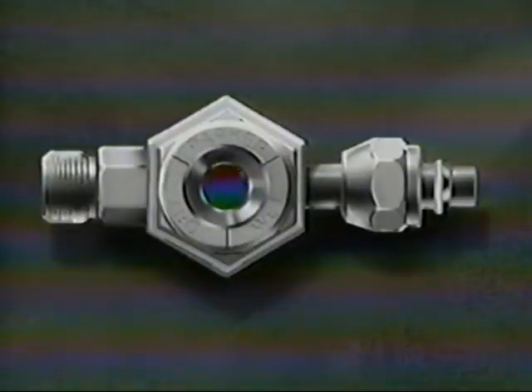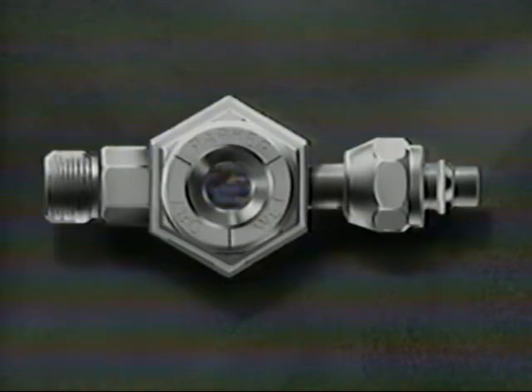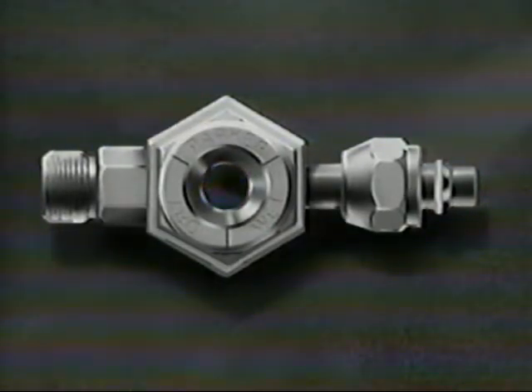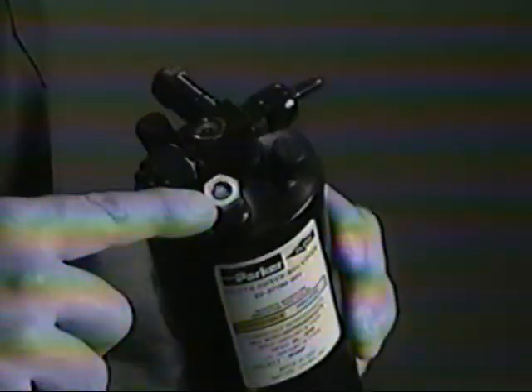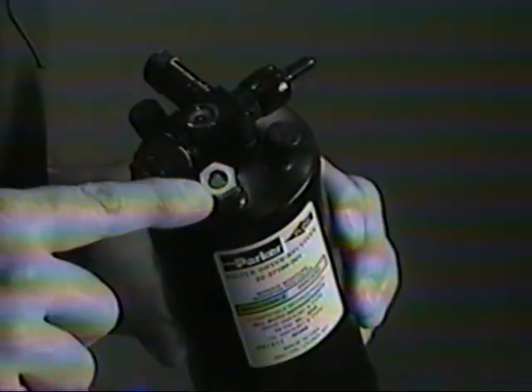Check the sight glass on the receiver dryer. Bubbles normally appear when the system is first started up, but should disappear quickly, although an occasional bubble may appear. A constant flow of bubbles could indicate that the system is low on R12. A clear sight glass normally means the system has an adequate charge. However, an overcharged system could also have a clear sight glass. A dirty or cloudy sight glass indicates a contaminated system. Oil streaks could mean an oil overcharge. Any moisture indicator color other than blue means that there is excess moisture in the system.